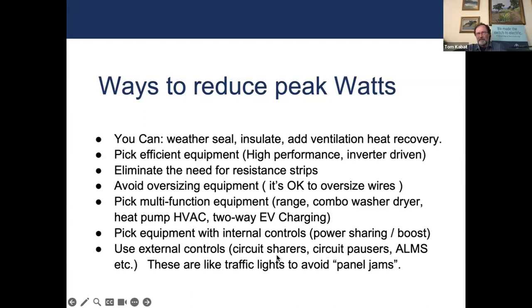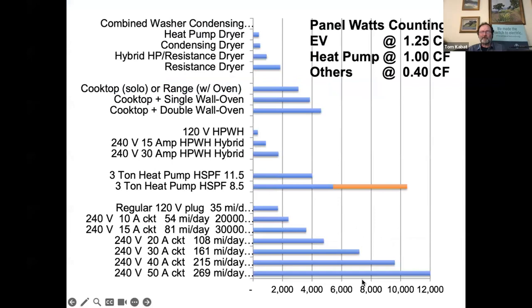I mentioned before these circuit sharers, and there's another type called a circuit pauser. It would pause the car charging, say if the whole panel got over 80% of its limit, then check back in 15 minutes to see if the panel is back under its limit, and if there's room to put the charger back on. There's also ALMS, which stands for automatic load management systems. You'll see some of those, but all those things are good for avoiding these panel traffic jams.